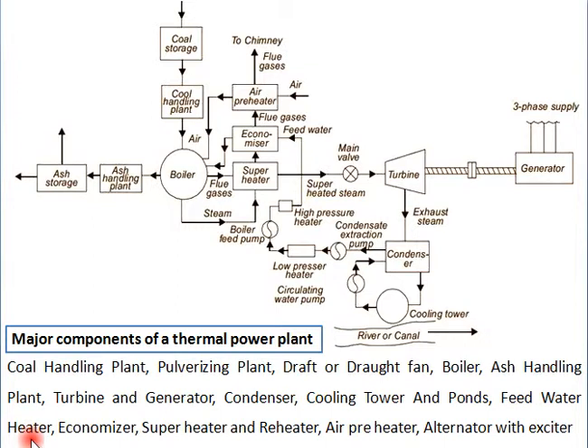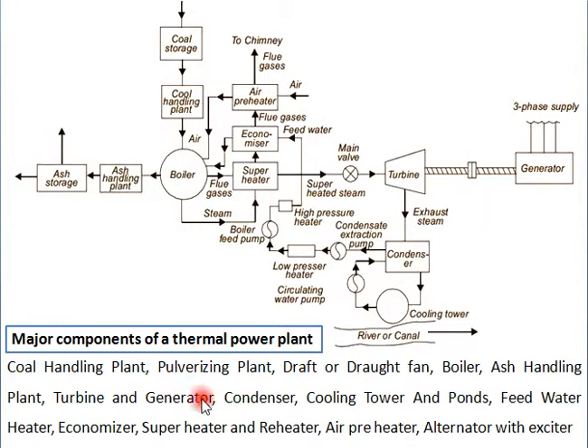There are two feed water heaters: one is the LP heater (low pressure heater) and the second is the HP heater (high pressure heater). The function of the LP and HP heaters is to increase the temperature of feed water with the help of steam extracted from different levels of the turbine. This feed water then comes to the economizer, which further increases the temperature of feed water using the flue gases coming out from the boiler.